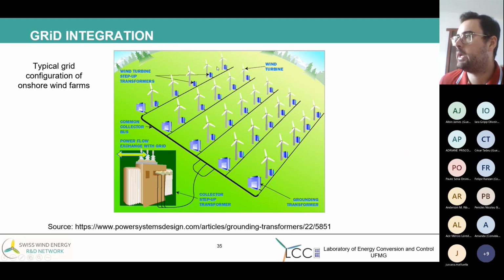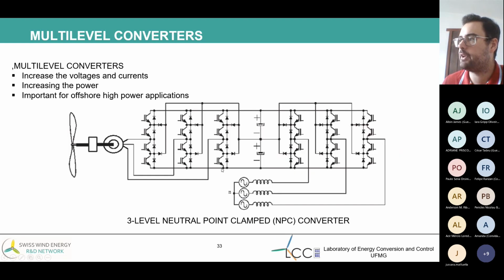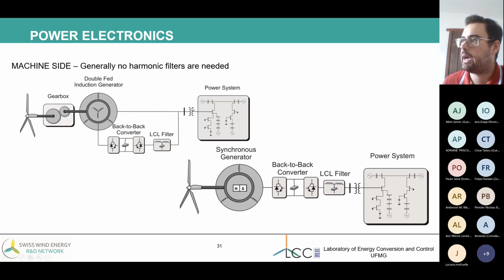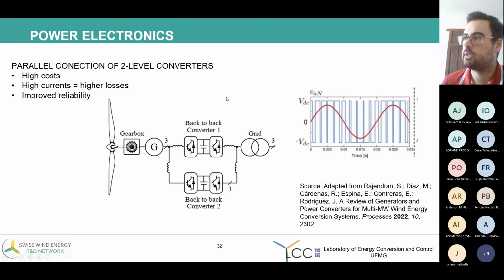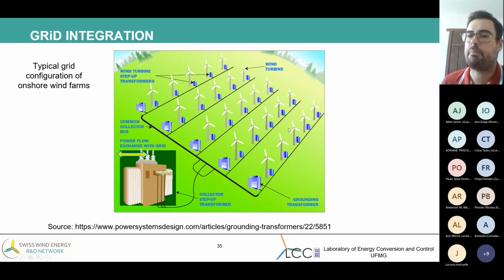I have several wind energy conversion systems. The distance between the turbines can be huge. I can have kilometers of distance between them. And so normally, at the output of the turbine, of the converter, I have the power filter, and after the power filter, I have a transformer. The objective of this transformer is to increase the voltage of the whole system of the converter to a higher voltage in the grid of the park.